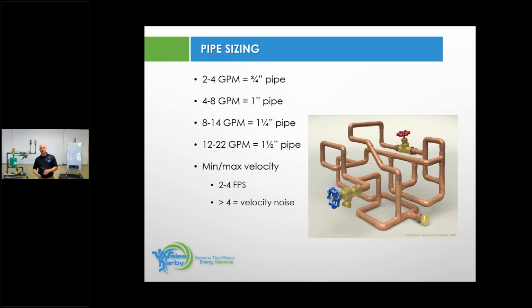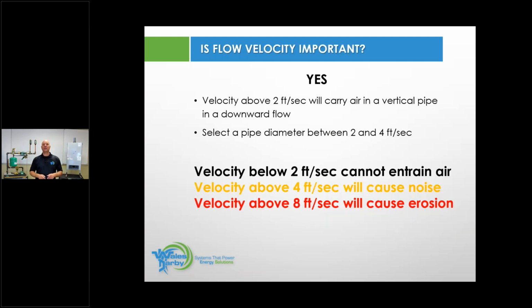So there's minimum flows we need to adhere to. There's maximum flows we want to adhere to. We want to make sure we're moving the water at the proper rate through these different heat circuits to make sure that we move any entrained air that may be out in that system. So velocity below 2 feet, I cannot move the entrained air. Velocity at 4 feet, that's like my limit. I will slowly start to cause a little bit of noise. At 6 feet, I will absolutely create noise. At 8 feet per second, I can actually erode pipe.